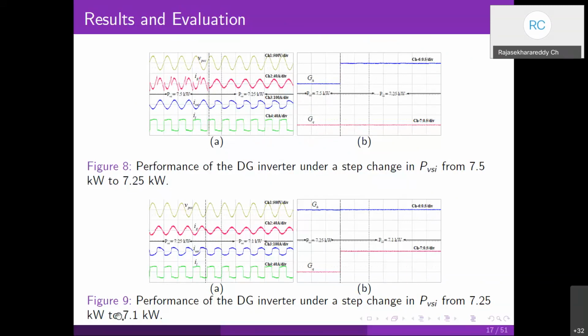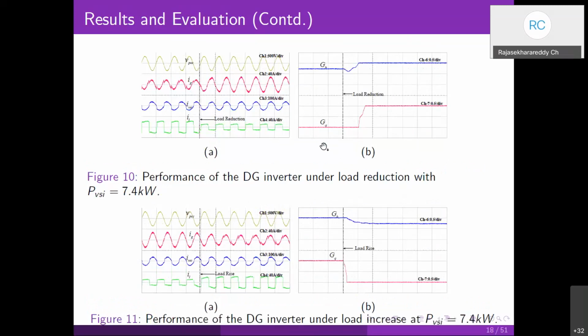Then in this figure 9, what is happening? The power generation of the voltage source inverter is further reduced, from 7.25 kilowatt to 7.1. Now you can see this GQ value, which is the reactive power compensation factor, has changed from 0 to 1. That means the inverter is now compensating both harmonic and reactive currents when the power generation is equal to 7.1 kilowatt. So in this control structure, as long as the inverter is not able to supply full harmonic currents, it will always set GQ to 0. That means it will not go for reactive current compensation. Okay, that was one case.